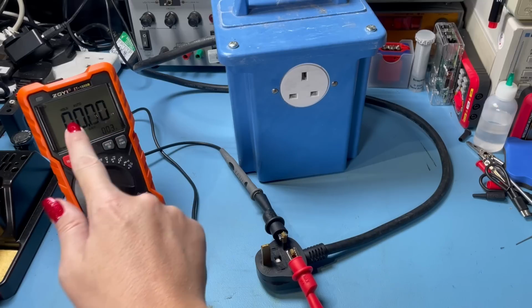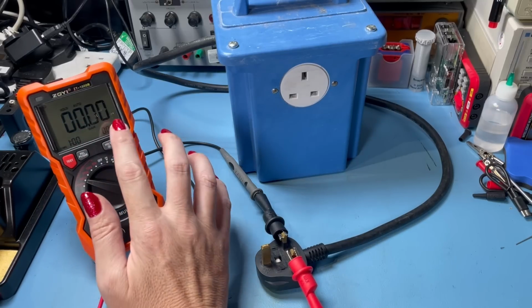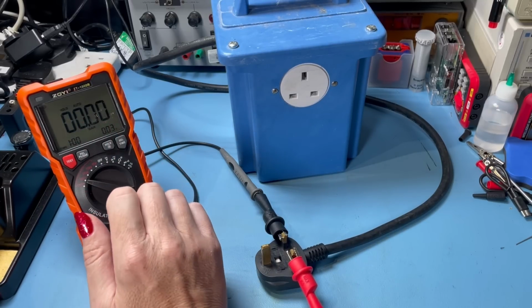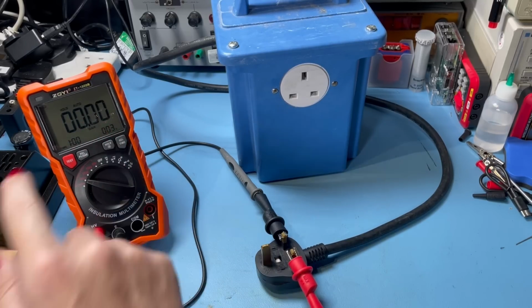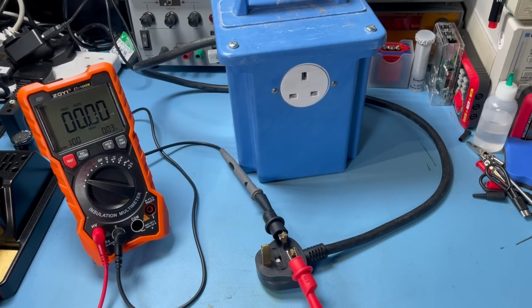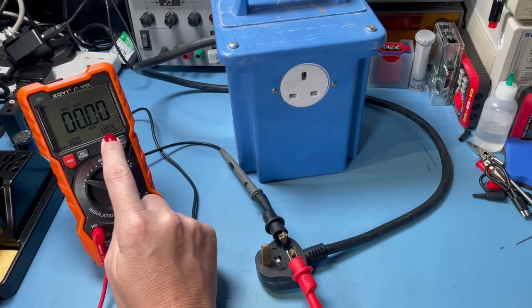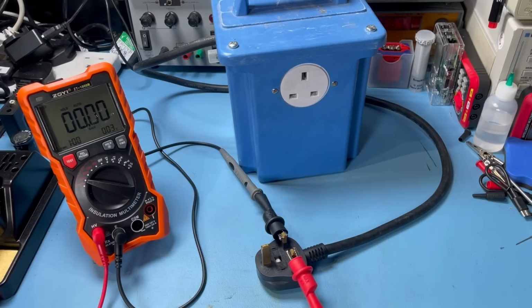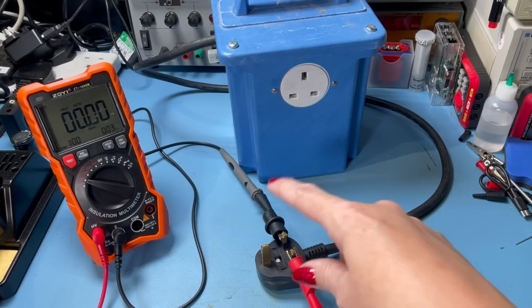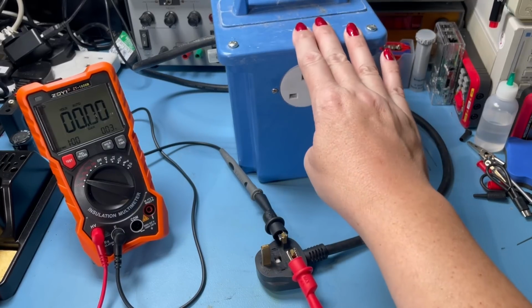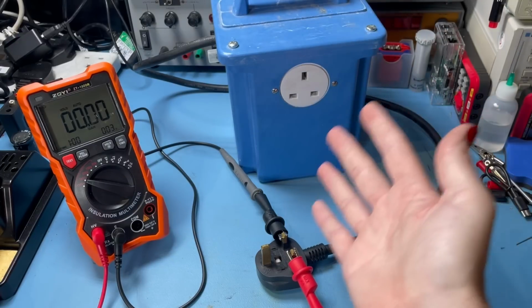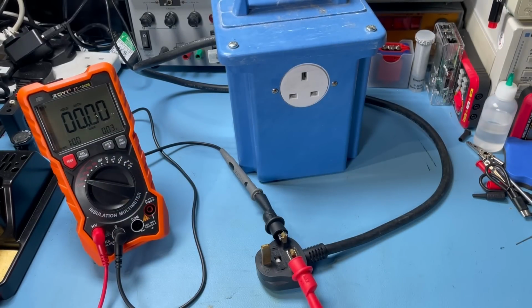As we suspected, 0. But did you see what the meter did there? Very clever. It did not put out the 500 volts that I'd asked it to. It's only put out 3 volts because it's recognized there was no resistance, because I'm just putting this voltage into the windings of this transformer. I don't need to put out 500 volts. Pretty clever. That also means I know my transformer works properly.